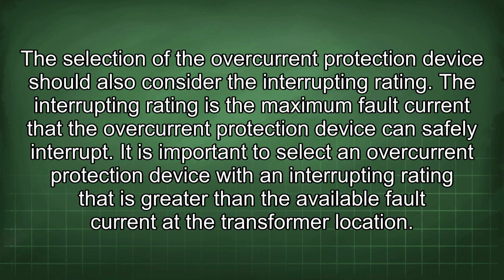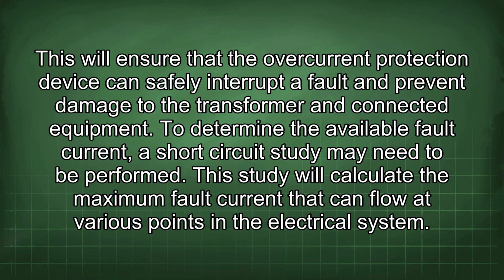The interrupting rating is the maximum fault current that the overcurrent protection device can safely interrupt. It is important to select an overcurrent protection device with an interrupting rating that is greater than the available fault current at the transformer location. This will ensure that the overcurrent protection device can safely interrupt a fault and prevent damage to the transformer and connected equipment. To determine the available fault current, a short circuit study may need to be performed.